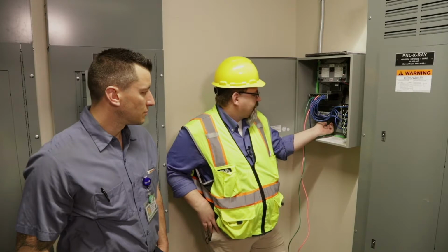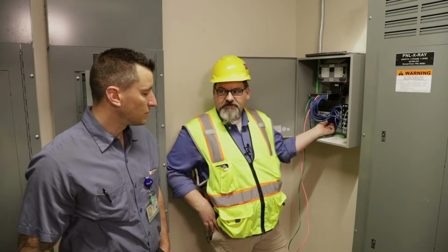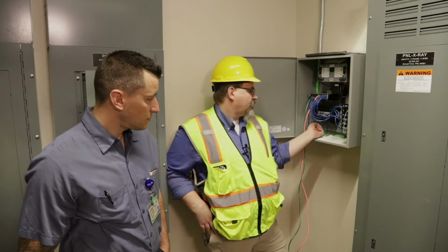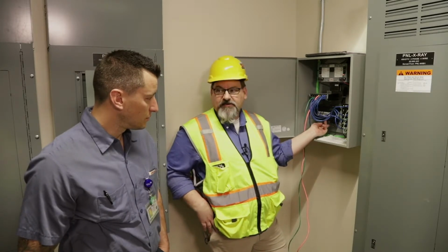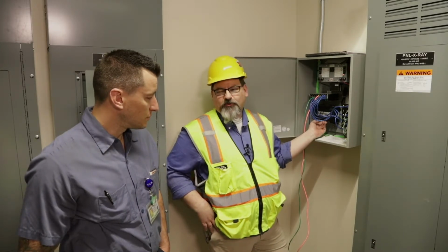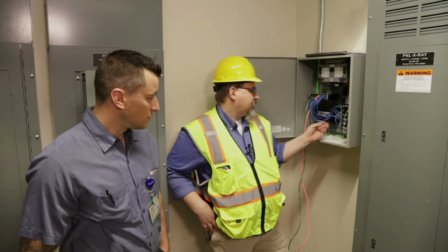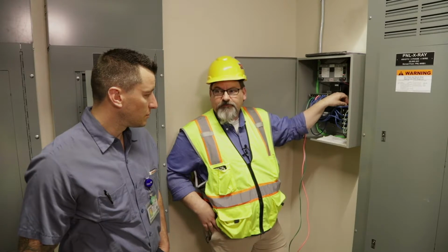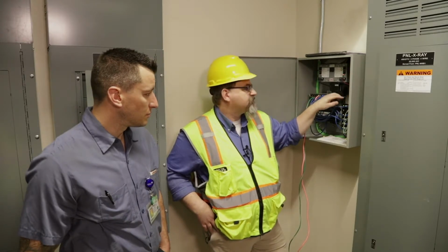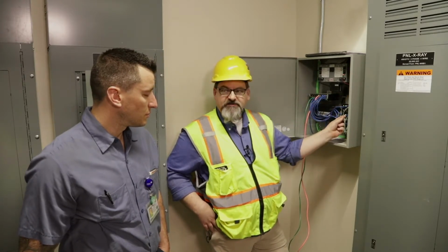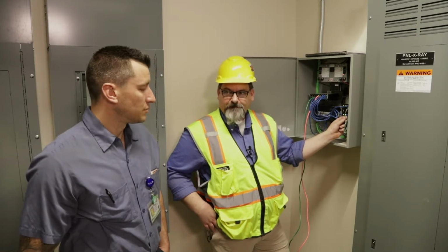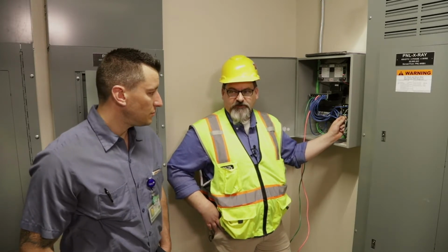If you need a network situation, you're going to plug a network cable down here to this one on the right-hand side. We're going to maintain this connection here to the middle port, which is port 2, is what we call it, right? And this port then speaks to these guys, which are routers, through this hub to the routers, and the routers speak MSTP BACnet to the various bridges for each room. Right, so like a bridge could be 3 rooms.